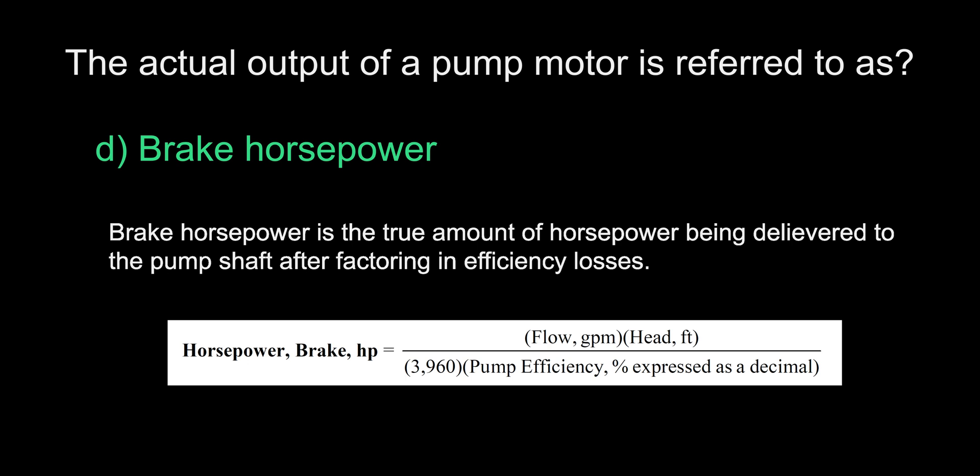The answer is D, brake horsepower. No pump can convert all its mechanical power into water power. This is due to friction losses in the bearings, water friction itself, and recirculation within the pump. To compensate for those losses, horsepower going into the pump shaft must be greater than the water horsepower leaving the pump. These additional power losses define the total brake horsepower requirement, BHP, at the pump shaft.